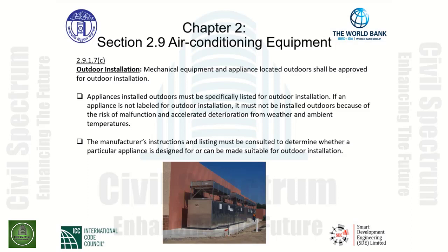As seen in the picture below, there is a compressor room that is listed for outdoor usage, and it has condensing units installed above the compressor room accordingly. All of the appliances and equipment in this installation are in fact approved for outdoor use.